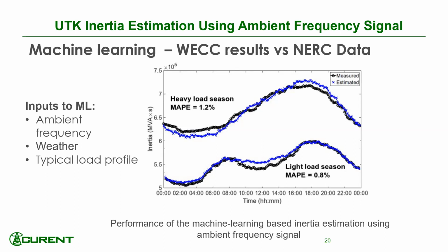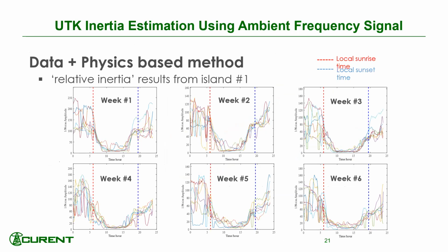And this is some results from estimation for the WECC system. It's compared to the ground truth, because NERC collects that information for the system as well. Okay, and you could probably guess what we're looking at here. This is inertia estimate from ambient frequency signal for a small island system. You can see you could have variations during the non-solar time, but during the day in the middle, when the solar is doing well, you have almost zero inertia. And I think that also shows the estimation using ambient data is quite interesting.